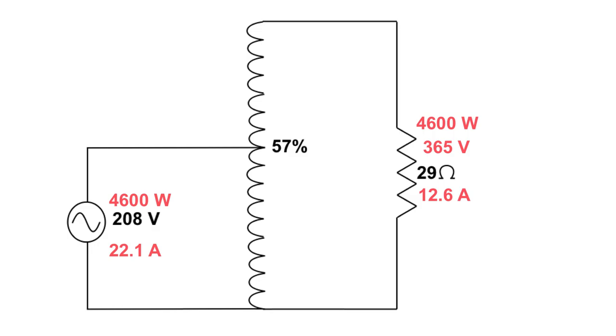Now the only thing left to figure out is the current that is going across this winding here, the common winding right up to this point right there. Now let's see what happens. We're going to move the 22.1 amps down to here, to this side. We're going to move the 12.6 amps down to this side. And just like when we talked about with the step-down autotransformer, I have 22.1 amps on this side of the node and 12.6 amps on this side of the node. It doesn't just suddenly magically lose that current, that 10-ish amps. It has to drop it across something. It's going to be dropping it across this winding, the common winding. So that's going to work out to be 9.5 amps.